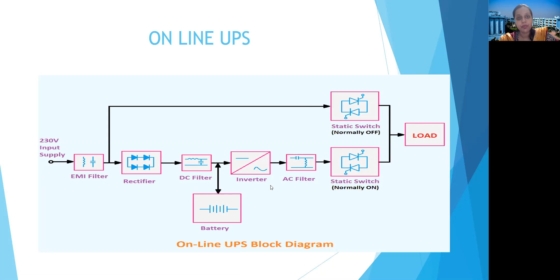What will happen? During the normally on condition, when the main is on, the AC input supply will charge the battery, similar to the offline UPS, and power will go to the load. Now when the main AC supply is cut off, this charged battery will provide power to the load. So there is no interruption of power in this type of UPS, and that is why these are known as online UPS.